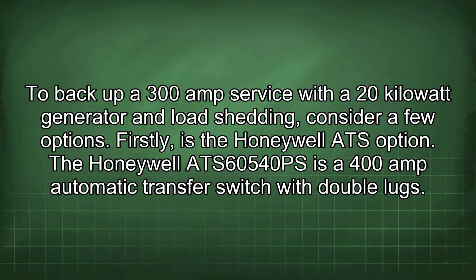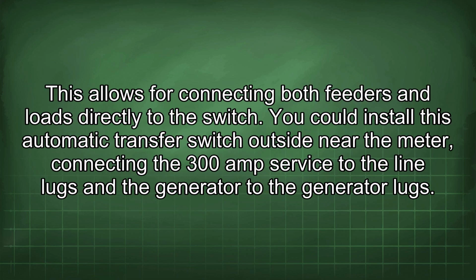To back up a 300 amp service with a 20 kilowatt generator and load shedding, consider a few options. Firstly is the Honeywell ATS option. The Honeywell ATS60540PS is a 400 amp automatic transfer switch with double lugs. This allows for connecting both feeders and loads directly to the switch.